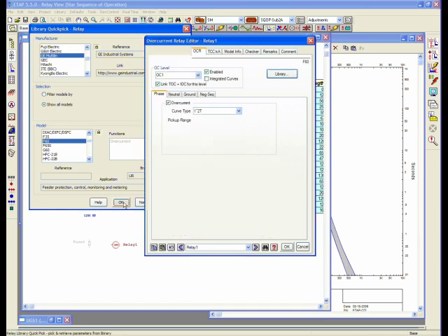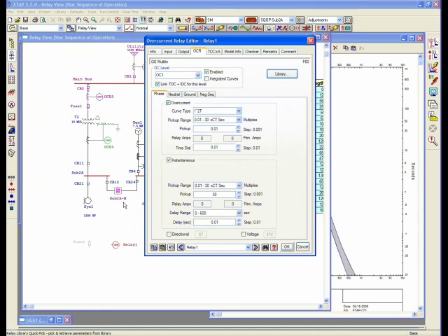Once I select this library from my QuickPick library, it will provide me the overcurrent settings and the instantaneous settings, as well as all the trip elements within that relay. This particular relay is a multifunctional or multi-trip element relay, which has phase, neutral, ground, and negative sequence.